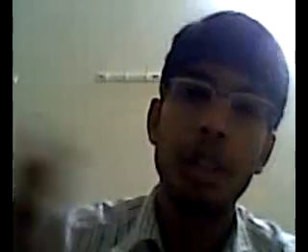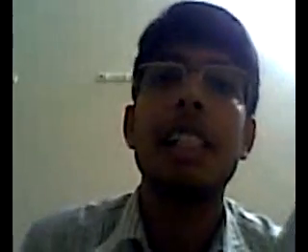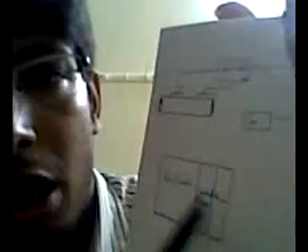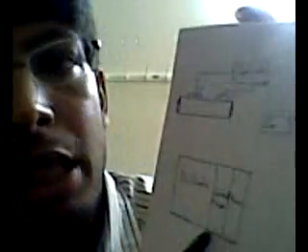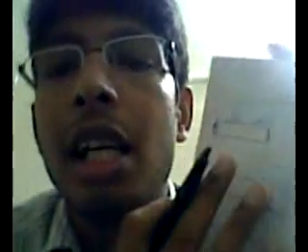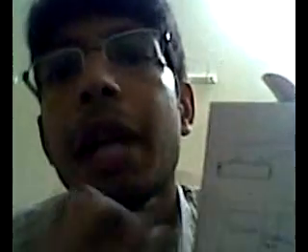Input and output cards are required because the value that comes from the field is very raw. Sometimes it has to be conditioned. Sometimes you might want voltages in the range of 1 to 5 or, let's say, 4 to 20 milliamps. Conditioning of the signal is required. I would say my IO card, that is input and output card, would do all these conditionings for me. So I have just divided this block into power, control, and the remaining space for placement of IO cards. This is the most basic diagram. Now we'll elaborate on this.